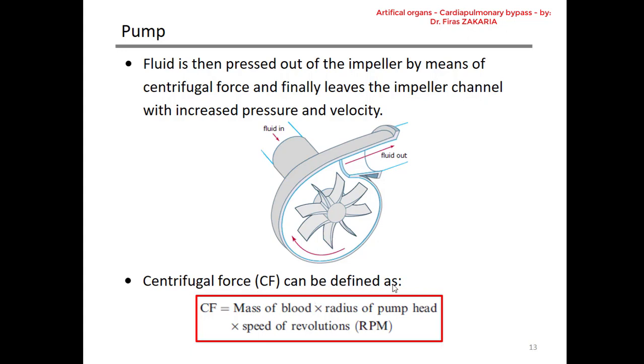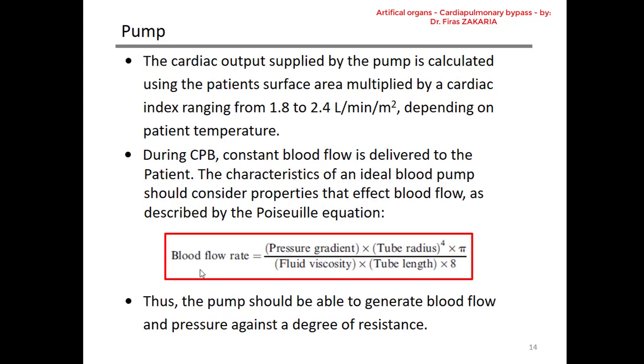Centrifugal force can be defined by this formula. Centrifugal force is equal to the mass of the blood times the radius of the pump head times the speed of revolutions, RPM. If we multiply these parameters, we obtain the centrifugal force. Also, one can calculate the blood flow rate. It depends on the pressure gradient, the tube radius, fluid viscosity, and tube length. So the blood flow rate is given by this formula. This is the Poiseuille equation.